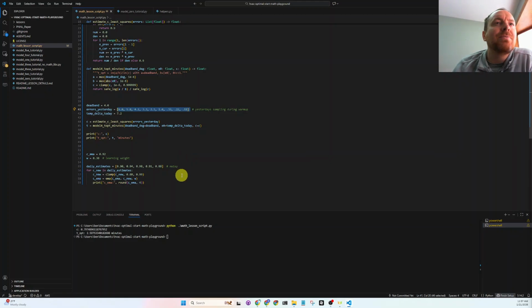So basically, when we ran our optimal start, our delta temperature was 6 degrees, and then 5 degrees, and then 4, and 3, then 2.5, then 1, and then slowly got up to zone set point. And over the course of 1, 2, 3, 4, 5, 6, 7, 8, 9 minutes, so this would have been a 9-minute warm-up cycle.